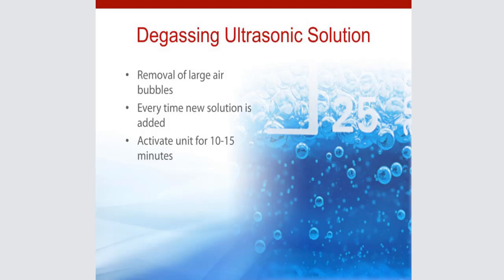The reason you want to get rid of those little gas bubbles is because they migrate to the cavitation bubbles, and it prevents the cavitation bubbles from imploding on themselves, and that's what loosens the debris on your instruments. So if you have extra gas bubbles in the solution, your cavitation is not going to be as efficient. Think of the gas like an airbag in your car, so it prevents it from contacting.